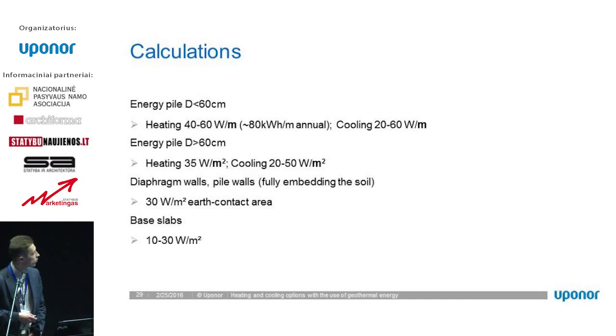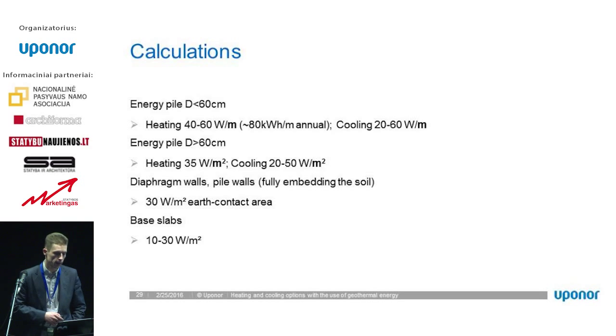If they are bigger piles, we are not talking about meters but square meters - what is the surface area of the pile, and how much energy can we get from it. Diaphragm walls or slurry walls put in the ground give around 30 watts per square meter. For base slabs - sometimes we use the slab under the building, the basement - we can also use this flat slab for cooling and heating, though the numbers are smaller, 10-30 watts.